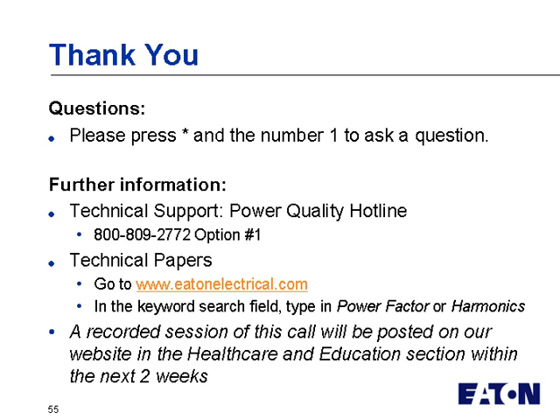Well, those are all good points. I think the part that we went through quickly, again, to show that there's a lot of variation on the size and type of power factor correction equipment, is that you can put in fixed and switched. Now, why do you put in switched? Just for those examples, Jack, if your load is not 24/7, like this office building here, we would typically have very light load on the weekend, maybe a third of the normal load. And that would be why you put a switched capacitor in.